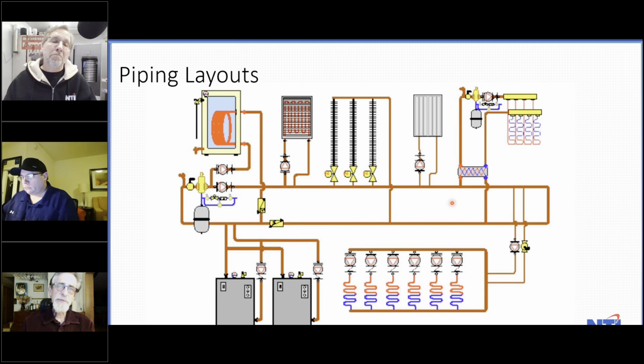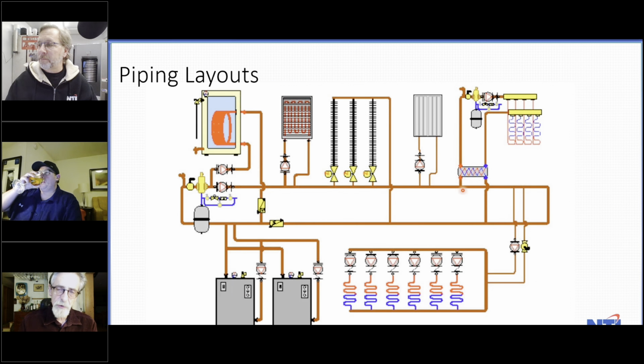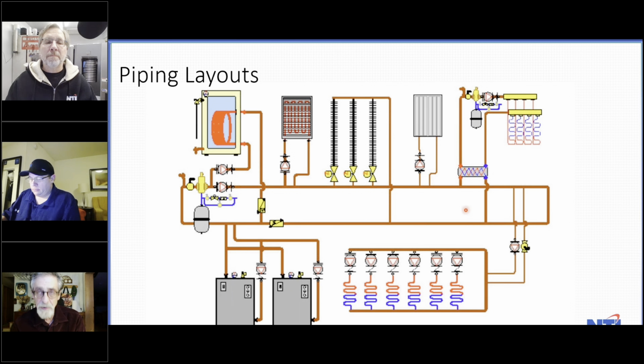35 or so. So if we're putting 150, let's say, into that heat exchanger, it's no problem getting 135 out to the system. Bear in mind, you never, like you said, 138. At 140, you can stress crack concrete, so you absolutely never want to be above that. And then finally, the low temperature radiant is the last takeoff on the primary loop.